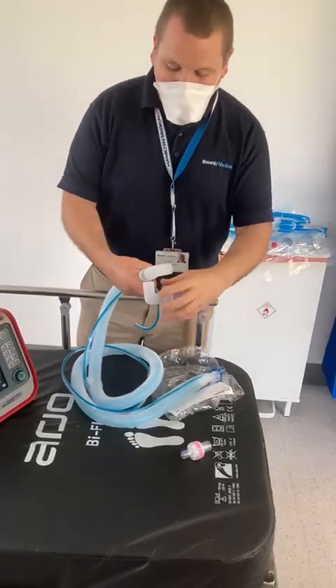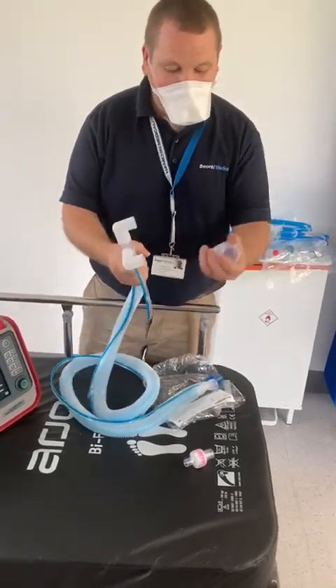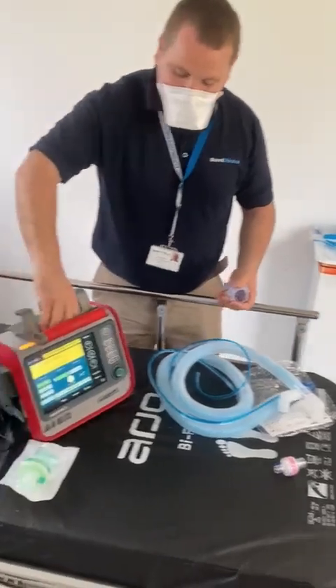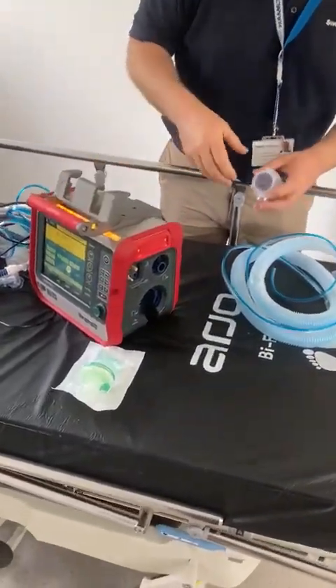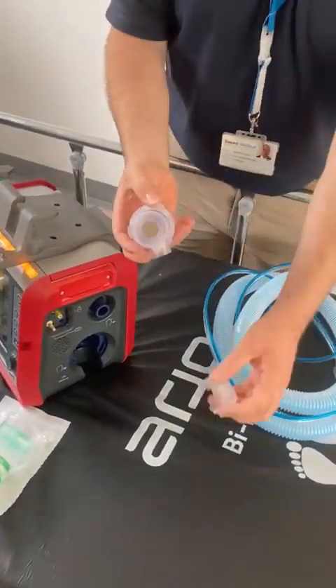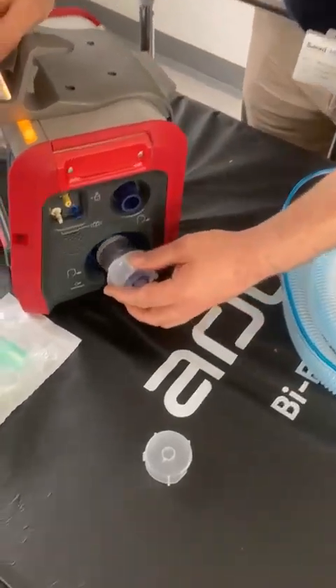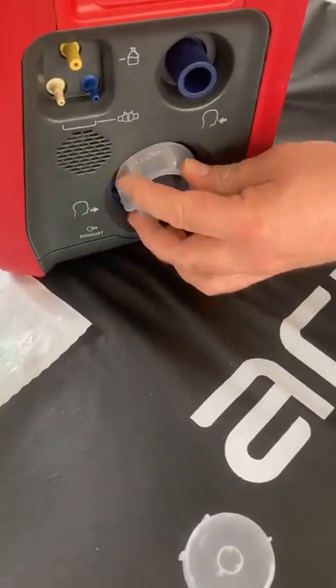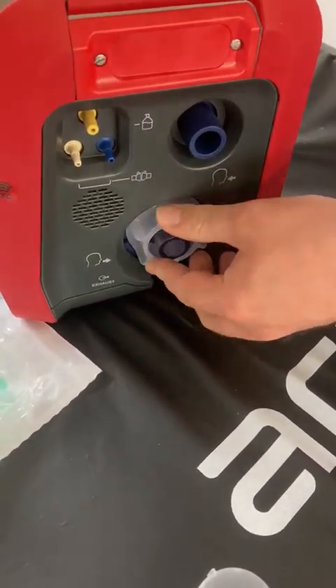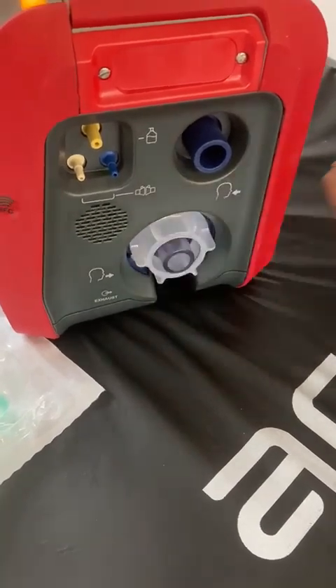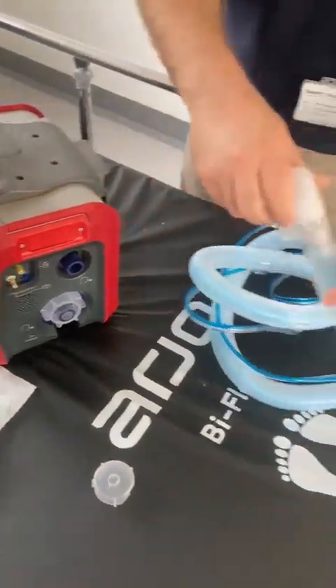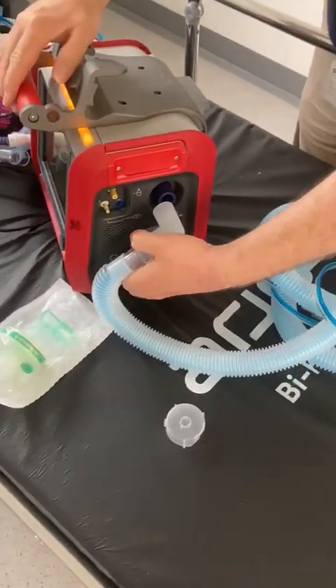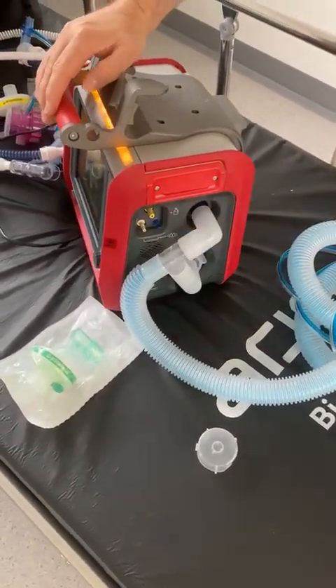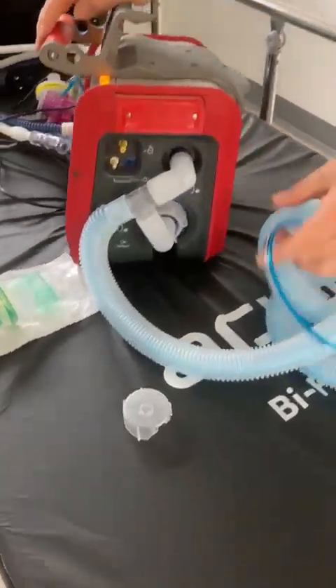So again, I always take off my expiratory valve when I'm putting it on the ventilator, because it's much easier to put on while it's not on the circuit. You take off your disposable cover, push it in, twist it anti-clockwise to make sure it's in fully, then give it a 1/10 turn clockwise to lock it in. Then my circuit pushes on the fixed elbow, like so.